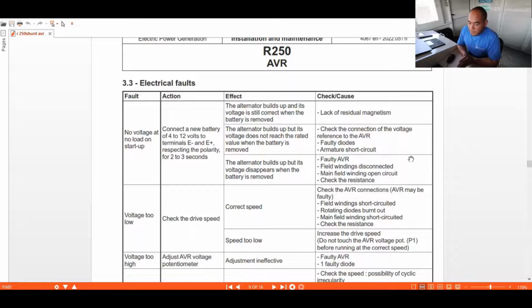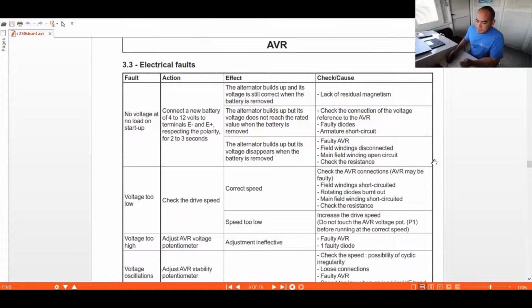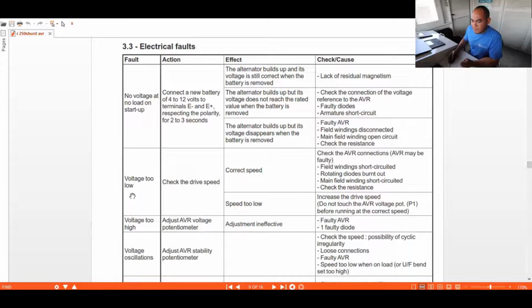The AVR itself, you have to check whether it is faulty, the winding connections, and the main field, whether it is open or in good condition. Also check the resistances of your windings. Okay, so for example, if the voltage is too low, check the drive speed. It means check whether the drive speed reaches the correct set points.